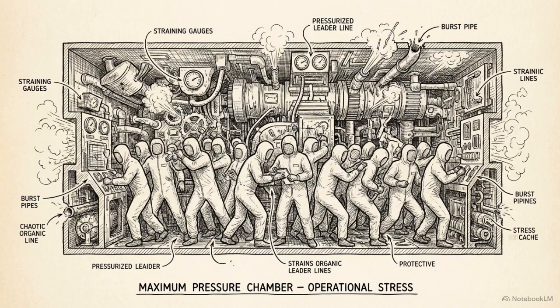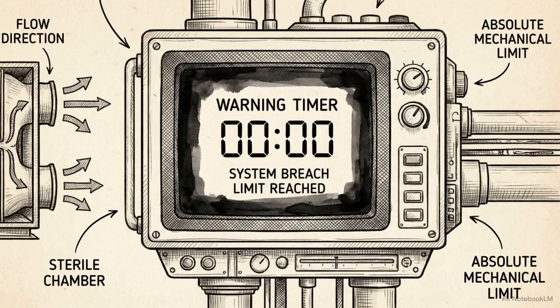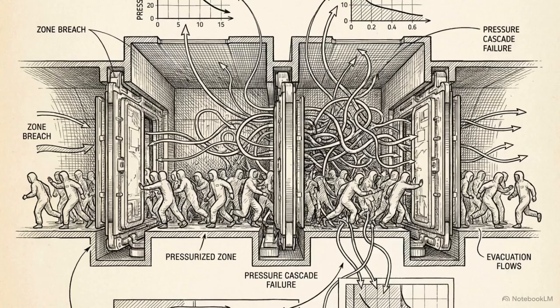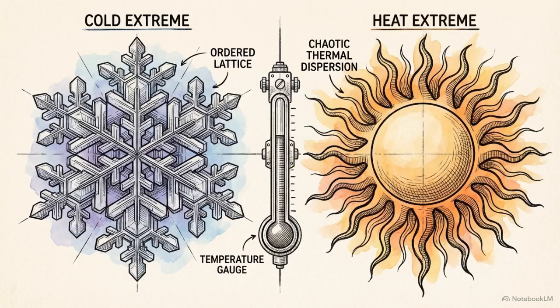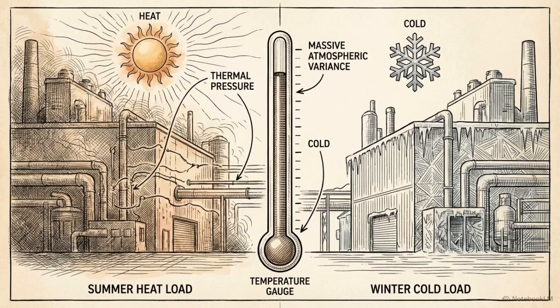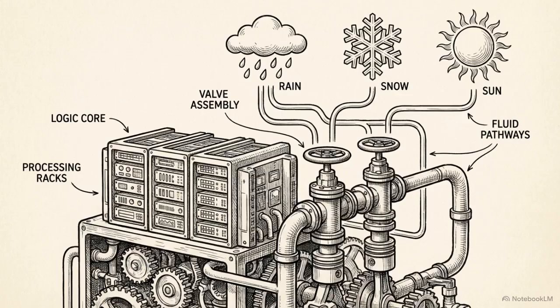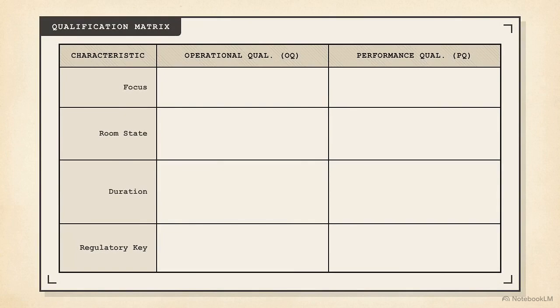The second PQ strategy involves worst-case scenarios. Engineers intentionally push the operational environment to its maximum planned stress capacity. This includes testing the room's recovery rate when the maximum allowable number of personnel occupy the space simultaneously. It also accounts for the stress of a shift change, where multiple doors are opening and closing in rapid succession, threatening the established pressure cascades. The third PQ strategy addresses seasonal variation. PQ is often split into multi-phase testing to account for external environmental extremes, comparing the atmospheric load of summer humidity against winter dryness. Surviving worst-case scenarios and seasonal extremes proves the HVAC system is intelligent enough to auto-correct against unpredictable environmental entropy.